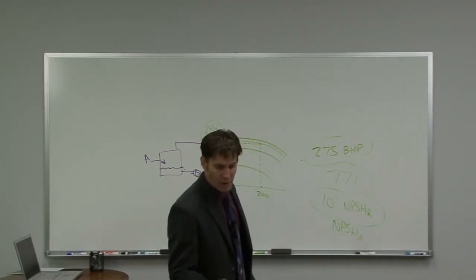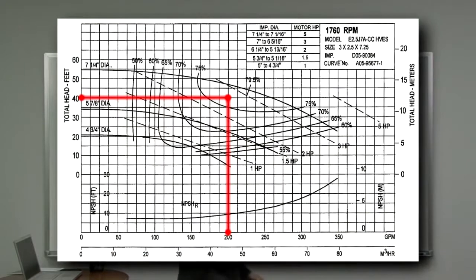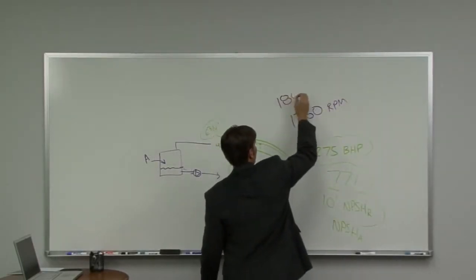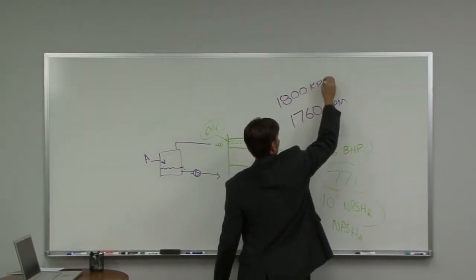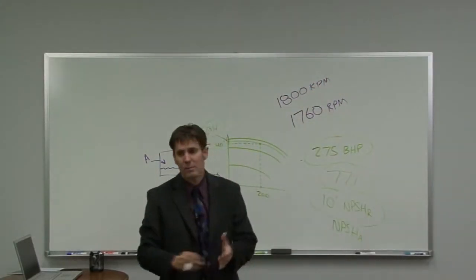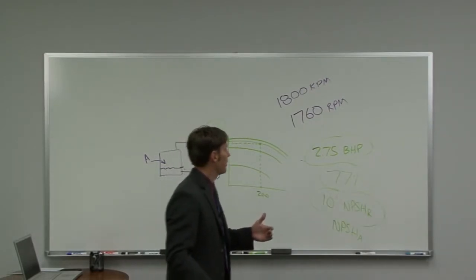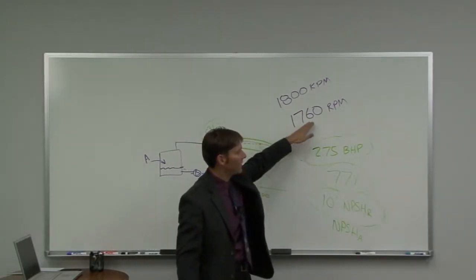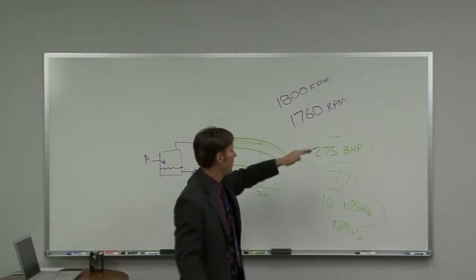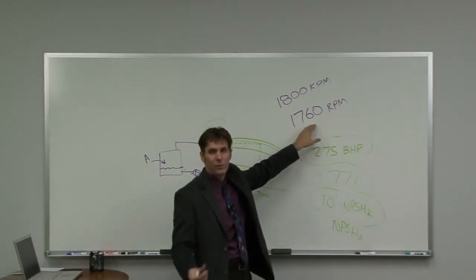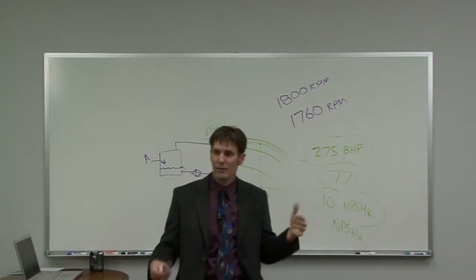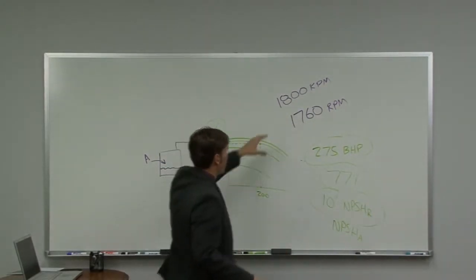The other important thing to note here is that this pump curve shows 1760 RPM. Now, I have a motor that's operating at 1800 RPM. And as we move higher and higher to more premium efficient motors, we see less losses. Back in years ago, we didn't even get to 1760. You might look at older pump curves that might be 1700, 1720, 1740 RPM. And this is losses because of the inefficiencies of the motor and the drive assembly. But this is operating at 1760.